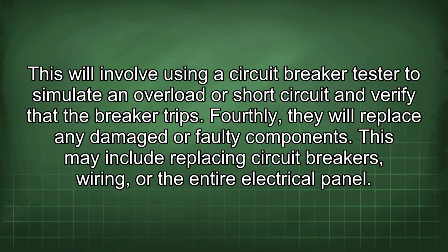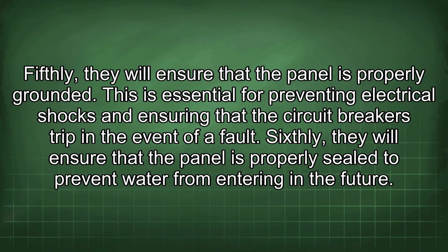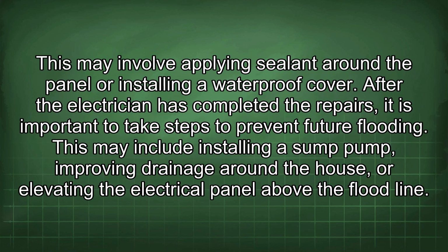trips. Fourthly, they will replace any damaged or faulty components. This may include replacing circuit breakers, wiring, or the entire electrical panel. Fifthly, they will ensure that the panel is properly grounded. This is essential for preventing electrical shocks and ensuring that the circuit breakers trip in the event of a fault. Sixthly, they will ensure that the panel is properly sealed to prevent water from entering in the future. This may involve applying sealant around the panel or installing a waterproof cover.